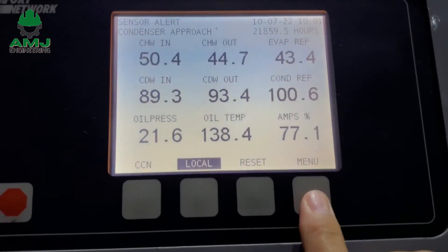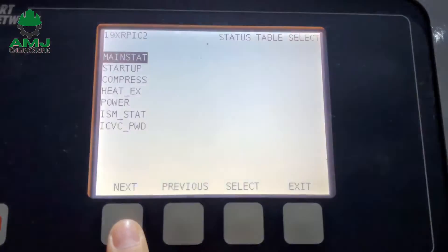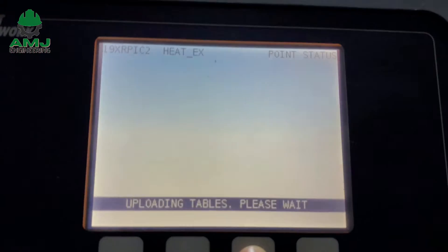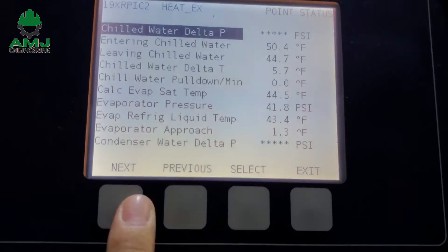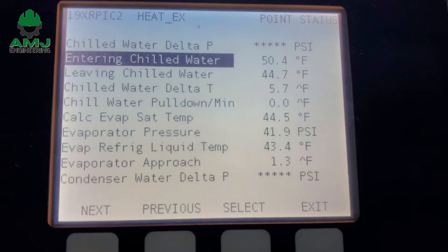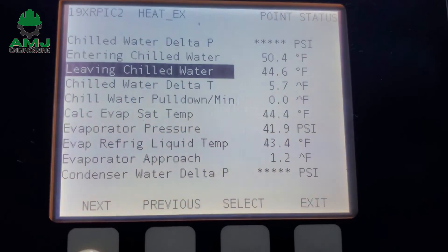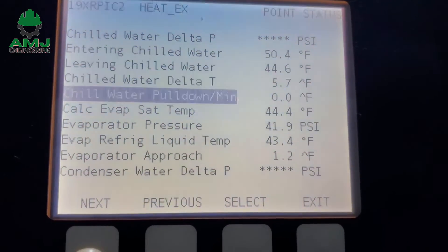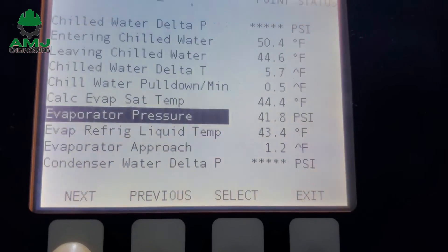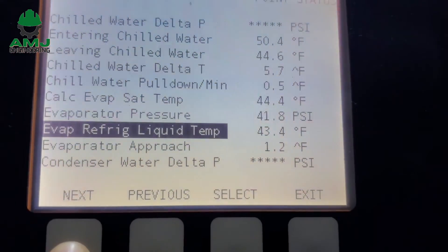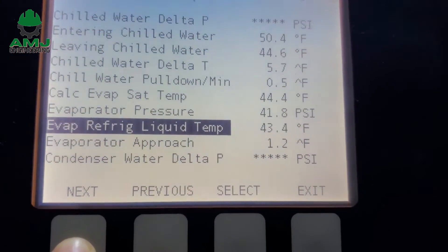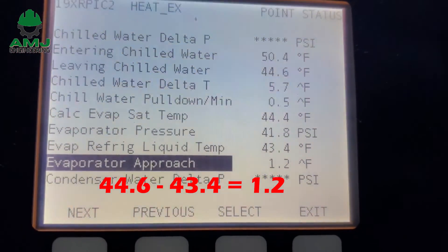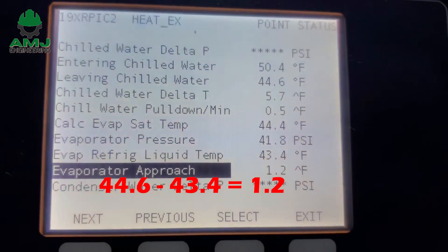The normal chiller evaporator approach is below 1.8 degrees Fahrenheit for well-maintained chillers. As we can see in this running chiller, the chilled water supply temperature is 44.6°F and the evaporating refrigerant temperature is around 43.4°F. This means the evaporator approach is 44.6 minus 43.4, which equals 1.2 degrees Fahrenheit.